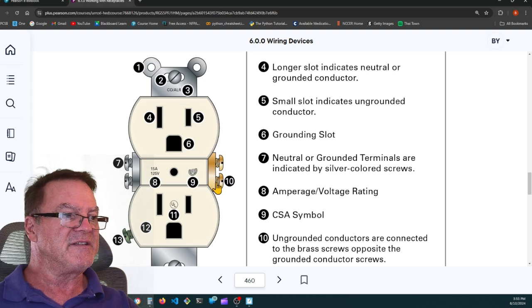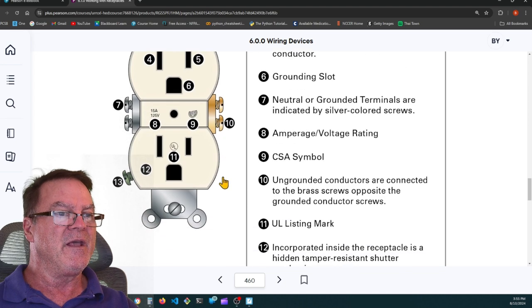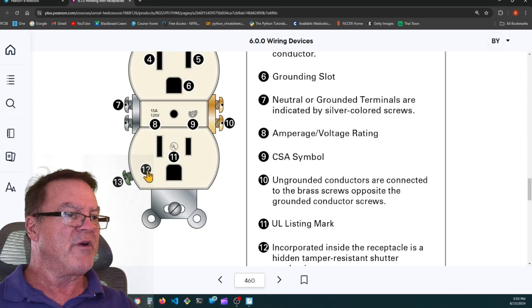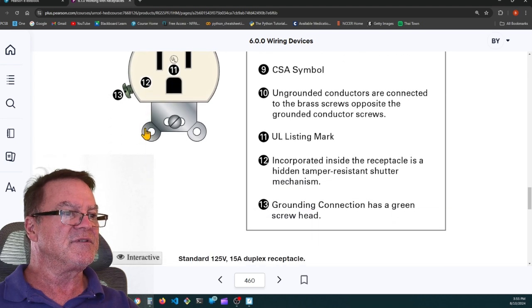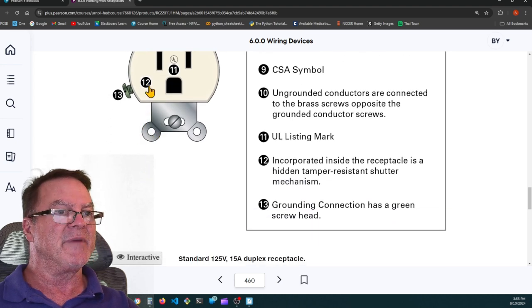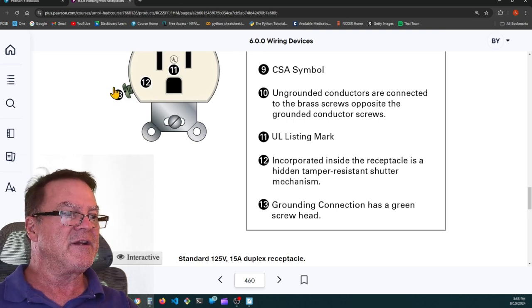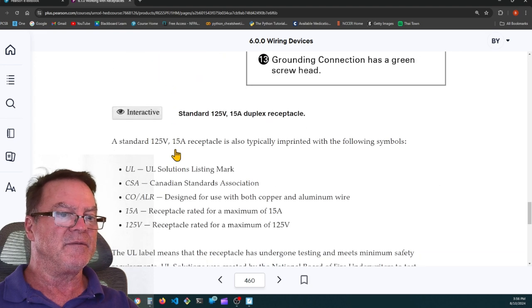Here, 10 is the ungrounded conductors are connected to the brass screws opposite the grounded conductor screws. 11 is the UL, Underwriters Laboratories listing mark. 12 is the hidden tamper-resistant shutter mechanism incorporated inside the receptacles. You can't see it, but it's in there. 13 is the grounding connection, has a green screw head.